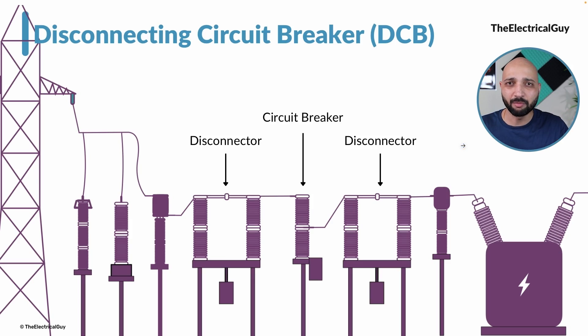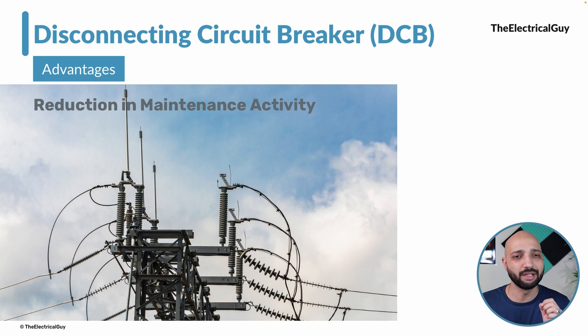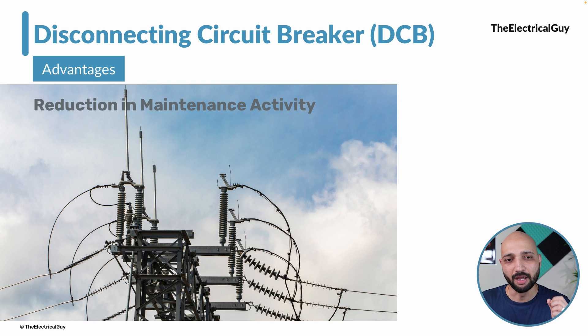The first and most important advantage is reduction in maintenance activity. When compared with a regular air-insulated disconnector, which needs maintenance every two to six years depending on user practice and atmospheric conditions, the disconnecting circuit breaker performs the disconnecting function inside the SF6-insulated chamber. So just like the circuit breaker, the DCB will not need any maintenance for 15 to 20 years — a significant reduction in maintenance activity.